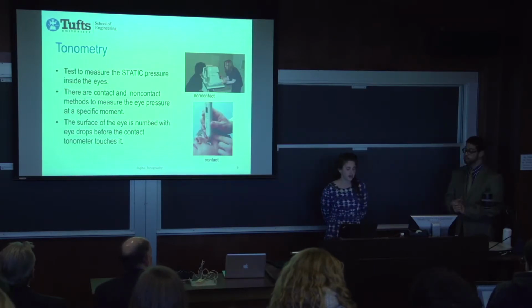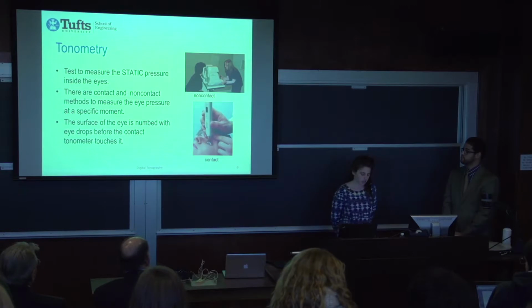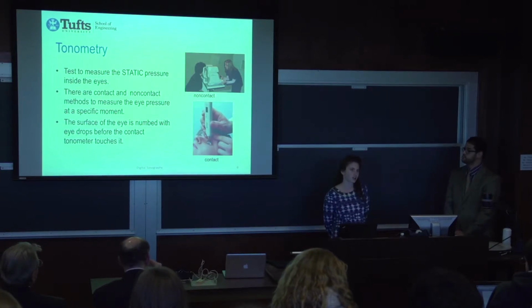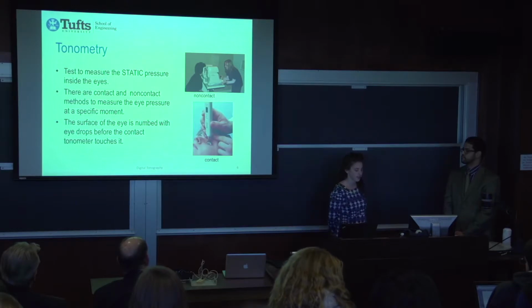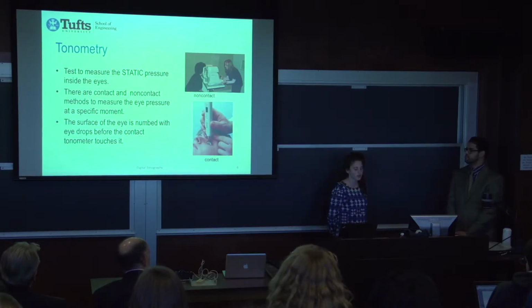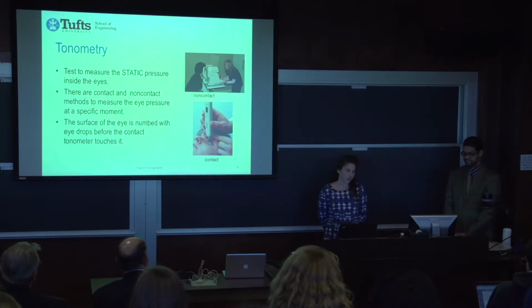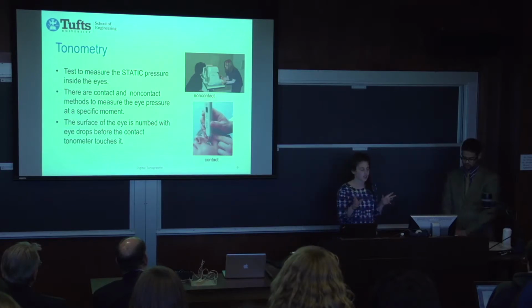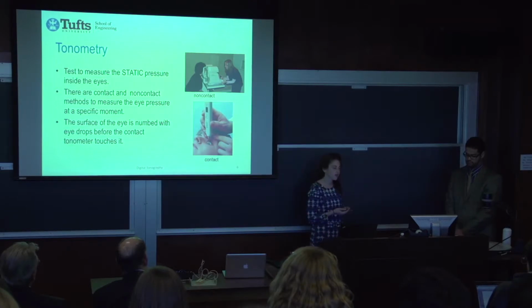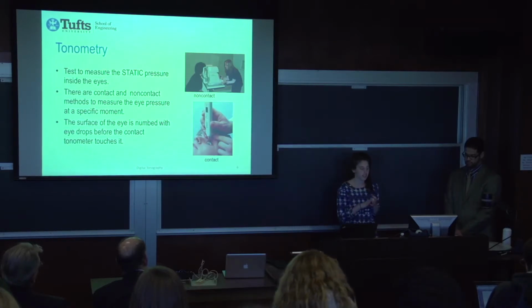Perhaps the most widely used method for doctors determining the IOP is a procedure called tonometry, which measures the force necessary to apply on a constant area of your cornea. Most tonometers are calibrated to measure pressure in millimeters of mercury. There are different kinds of tonometer devices, which you can group into two categories, contact and non-contact. We will quickly describe three methods, the first two of which are contact.